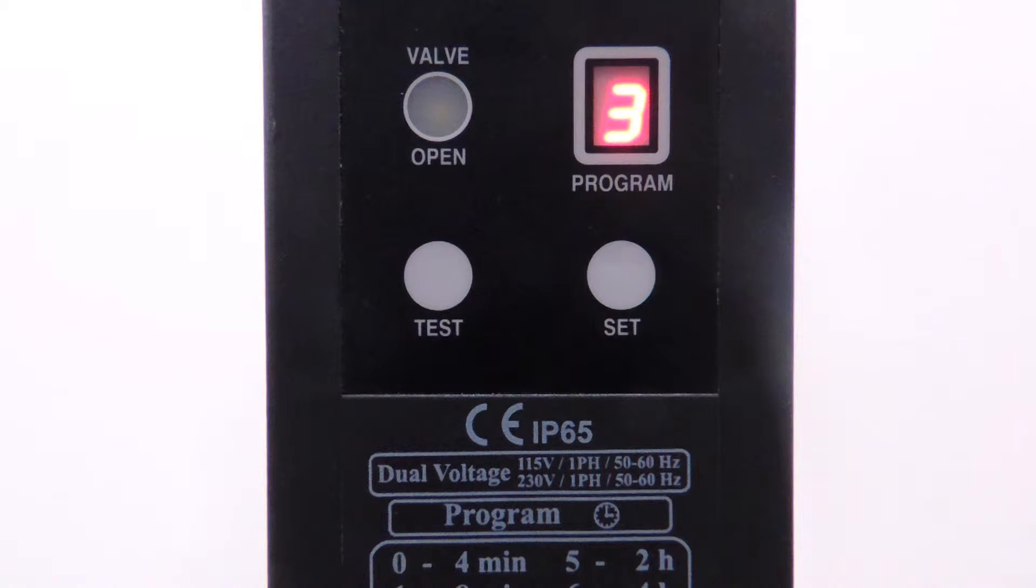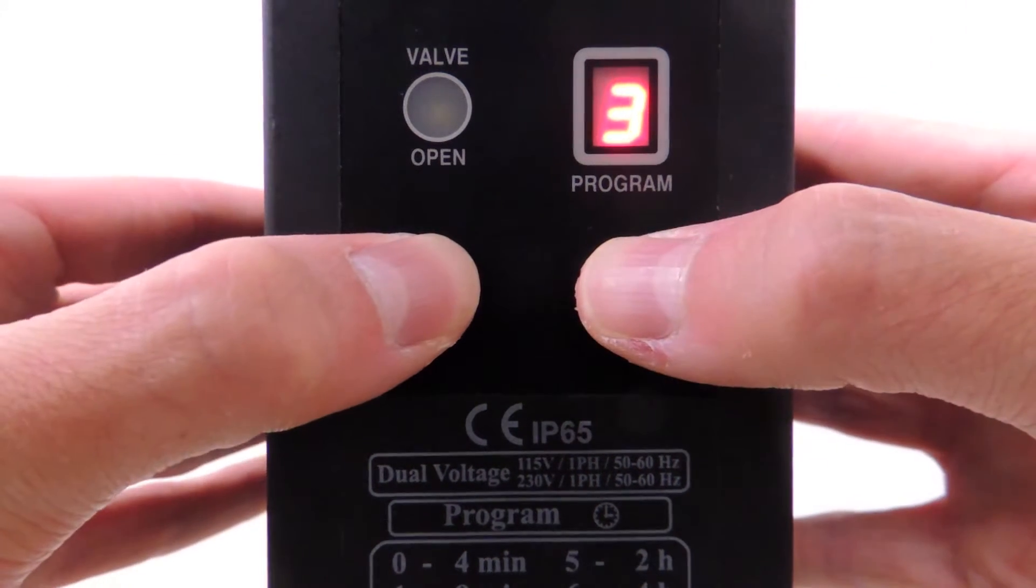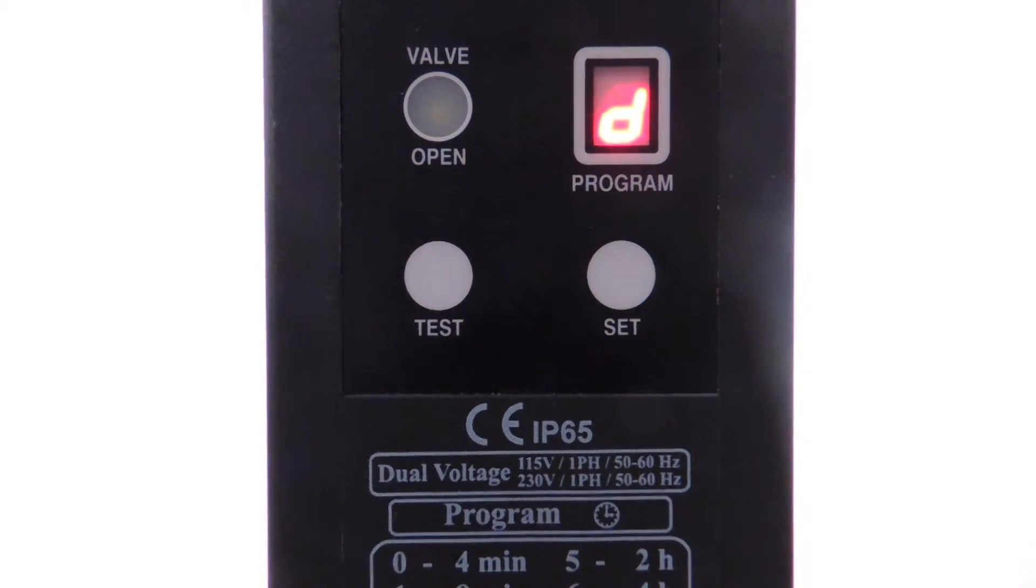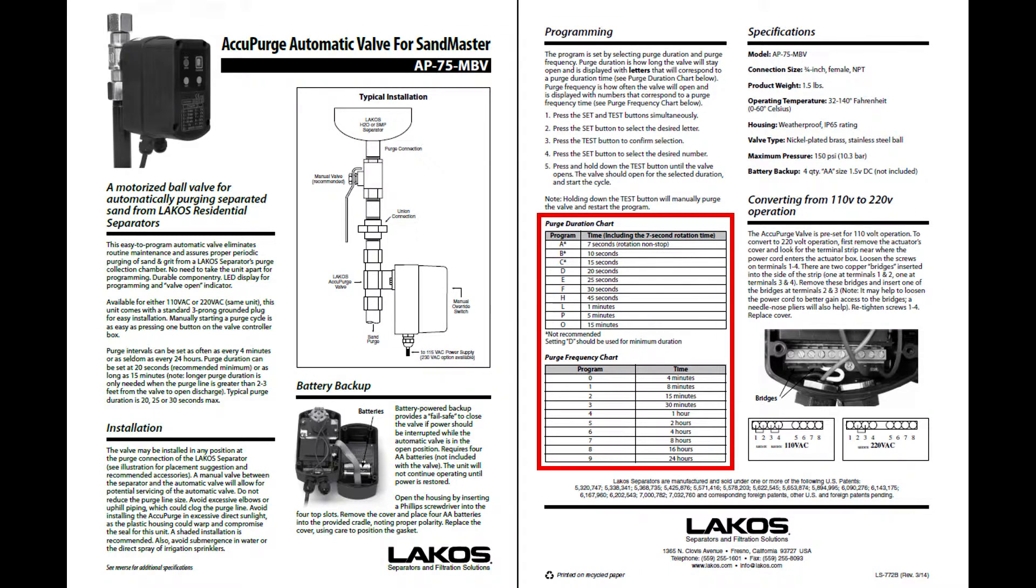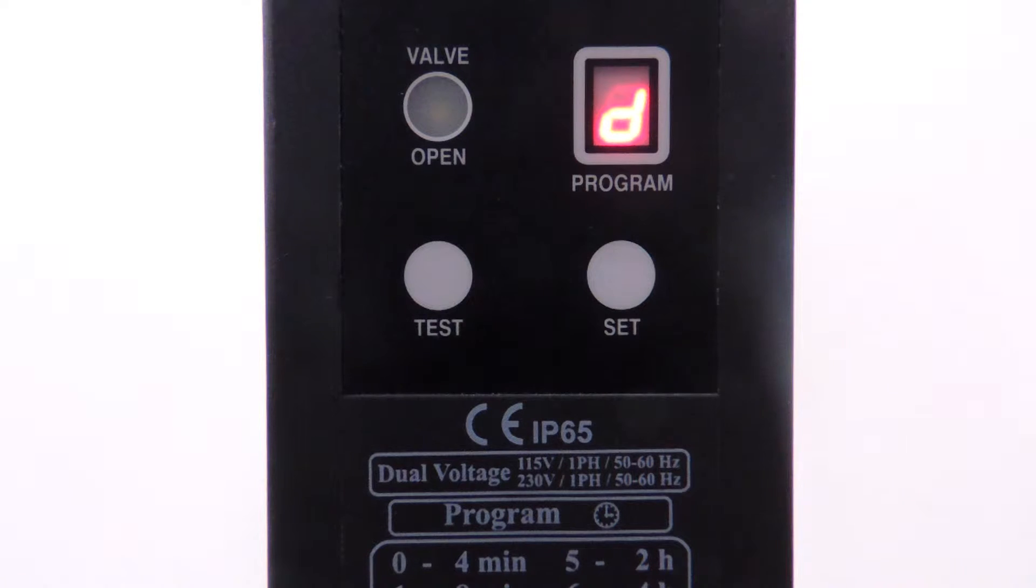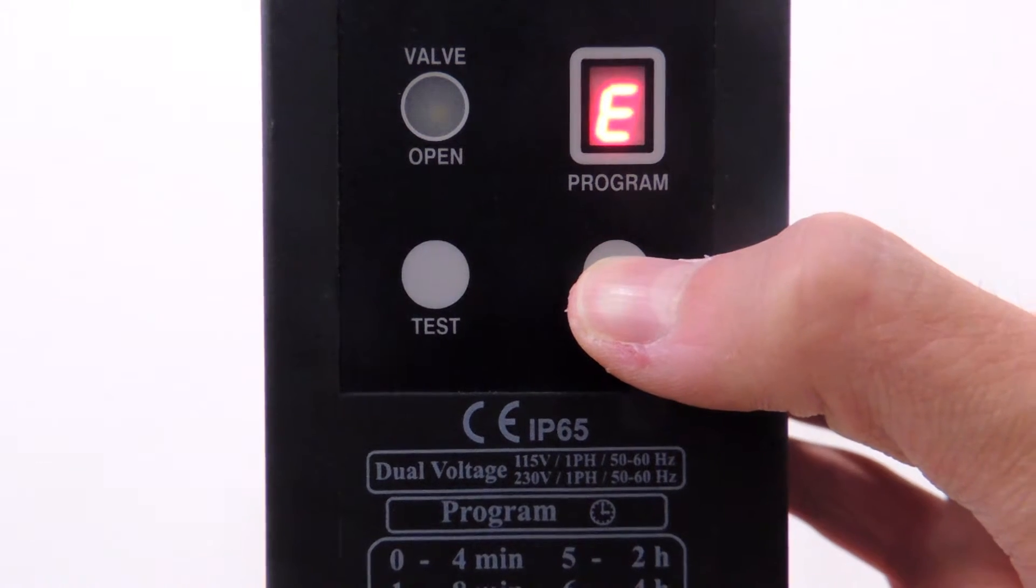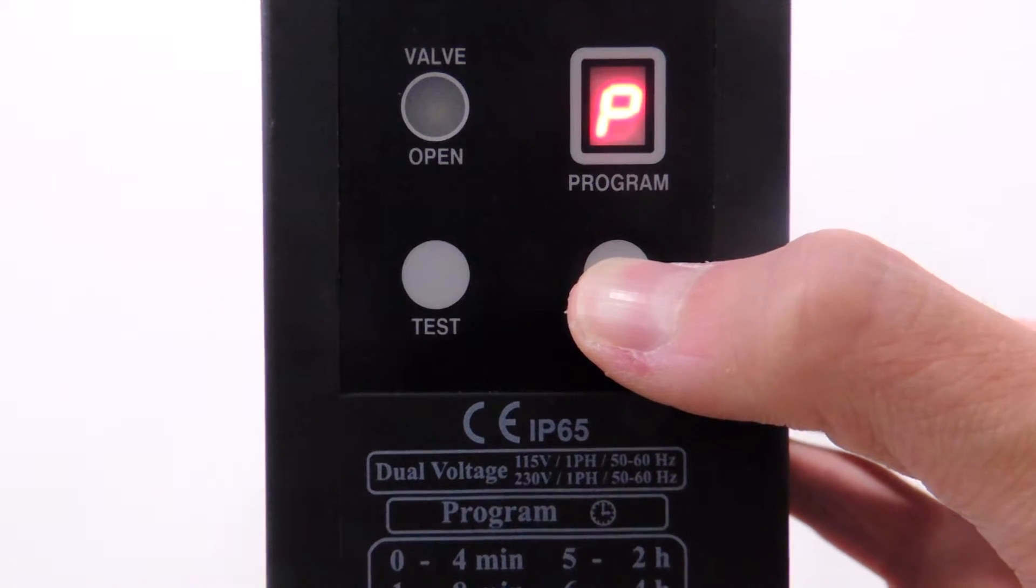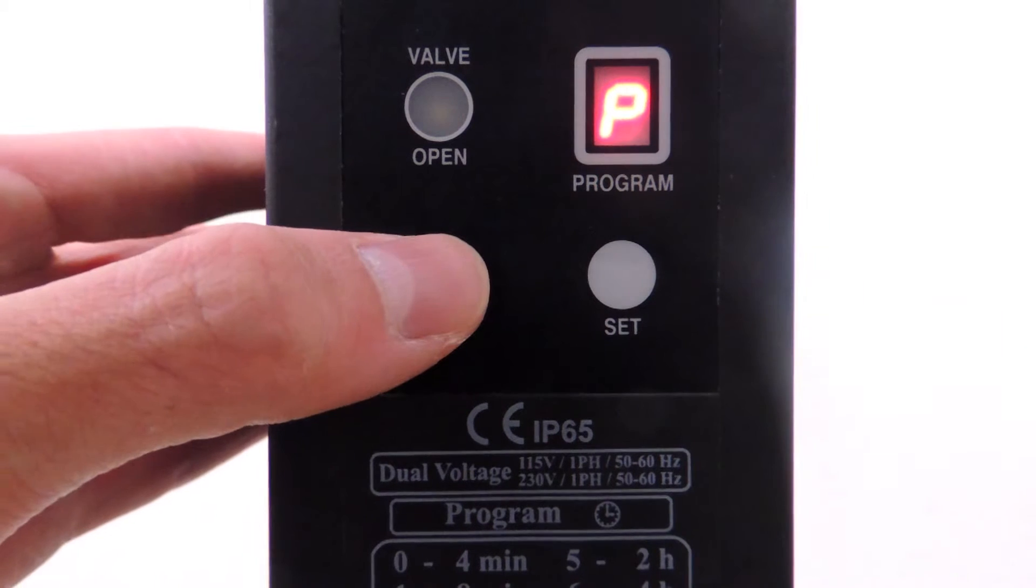The purge duration settings can be accessed by pressing the set and test buttons at the same time. The settings are displayed as letters. These letters correspond to purge duration times found on the purge duration chart in document LS772, which came with your product. Press set to cycle through the purge duration settings and press test to confirm the selected purge duration length.